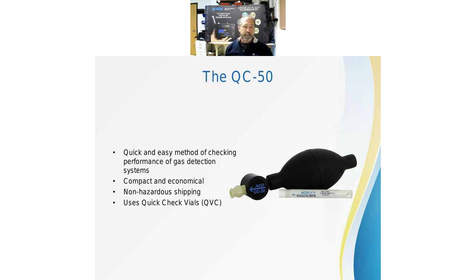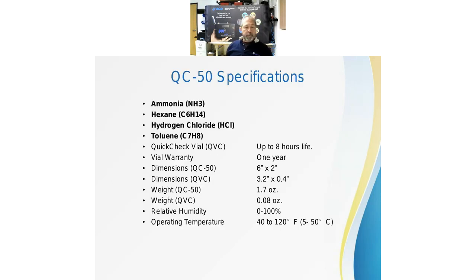Here's another bump tester we have. It's called the QC50. We've got these in some other gases that we could not make good calibrators out of. So at least we have a way to check. You see that vial that's in front of the unit. Inside there is a sealed glass ampule. And what you do when you're about to use this thing is you break that ampule, you insert it into that unit right there. This is a very low cost unit for functionally testing sensors. And then there's a little squeeze bulb there that you just squeeze to deliver gas out. It comes with a hose that attaches on the end of it. And you put your calibration cup on the end and functionally test whatever gas it is. So these gases are different than the other ones for the mini bump. So this is the gases we can do here: ammonia, hexane, HCl, and toluene.